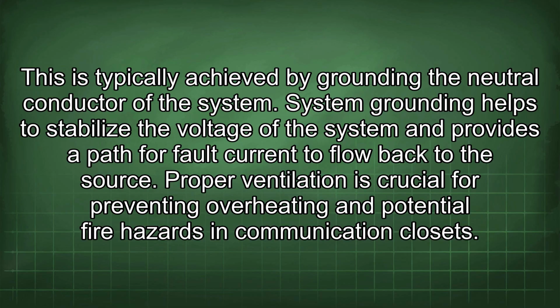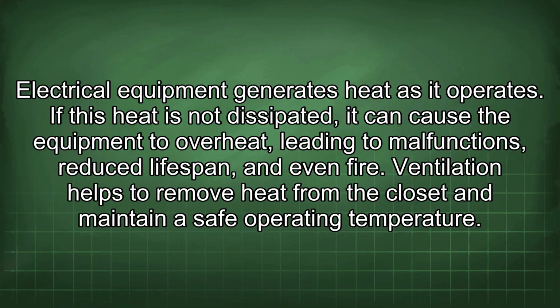to the source. Proper ventilation is crucial for preventing overheating and potential fire hazards in communication closets. Electrical equipment generates heat as it operates. If this heat is not dissipated, it can cause the equipment to overheat, leading to malfunctions, reduced lifespan, and even fire. Ventilation helps to remove heat from the closet and maintain a safe operating temperature.